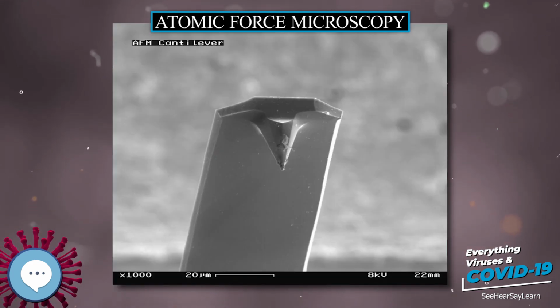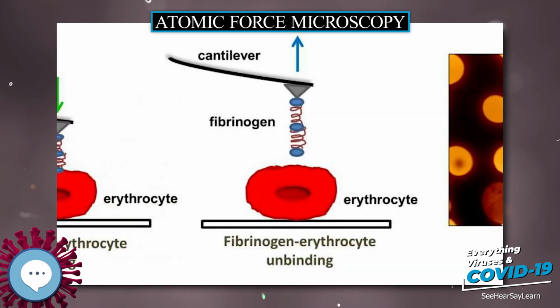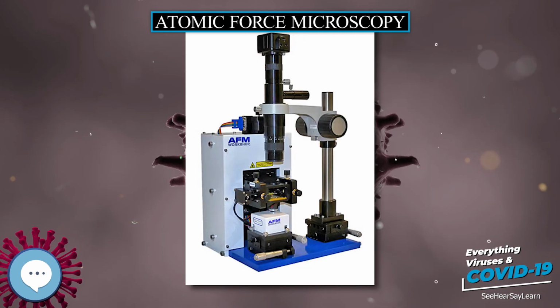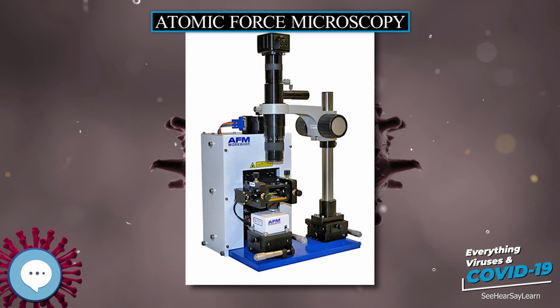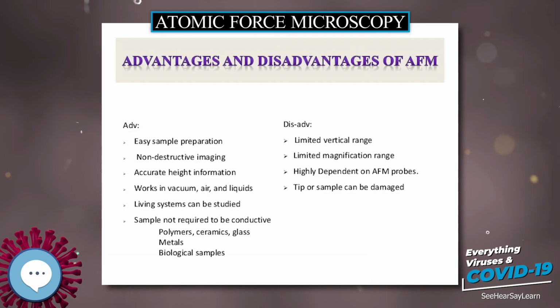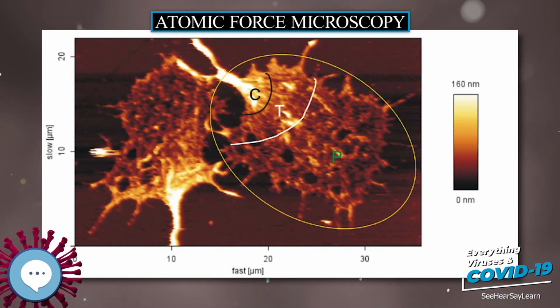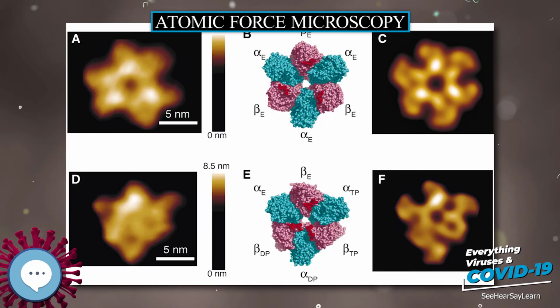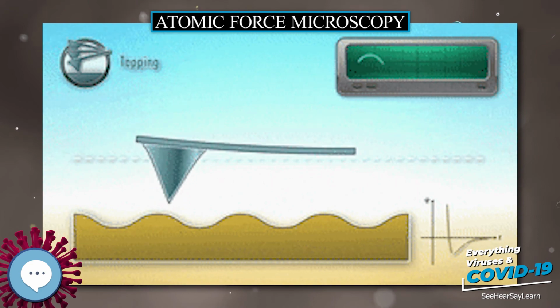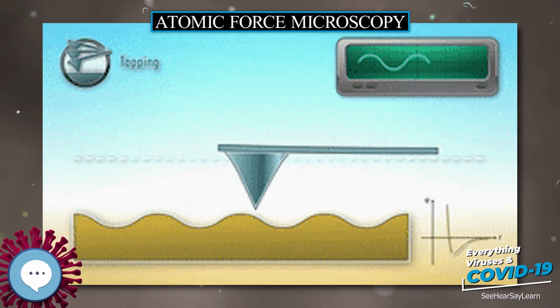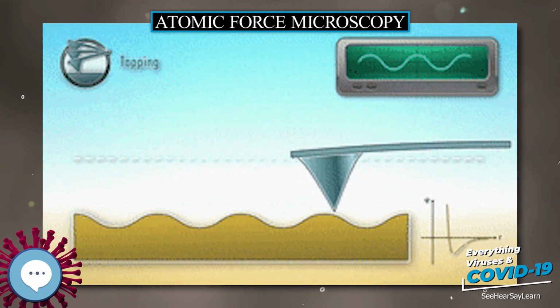Image formation. Note: the following paragraphs assume that contact mode is used. See section imaging modes. For other imaging modes, the process is similar, except that deflection should be replaced by the appropriate feedback variable. When using the AFM to image a sample, the tip is brought into contact with the sample, and the sample is raster scanned along an XY grid, Fig. 4. Most commonly, an electronic feedback loop is employed to keep the probe-sample force constant during scanning. This feedback loop has the cantilever deflection as input, and its output controls the distance along the z-axis between the probe support, 2 in Figure 3, and the sample support, 8 in Fig. 3.